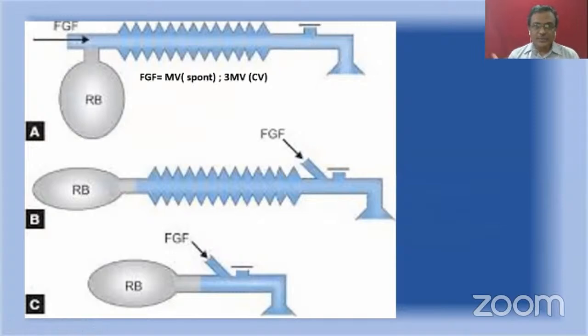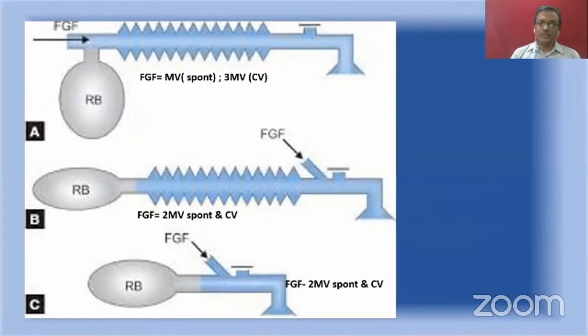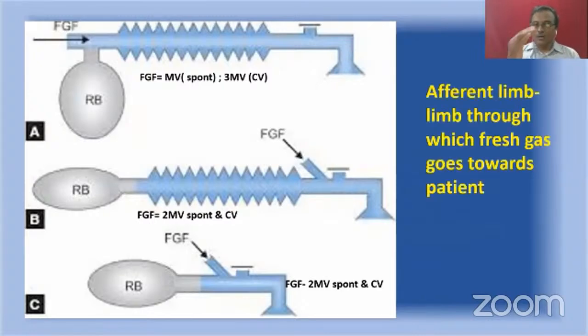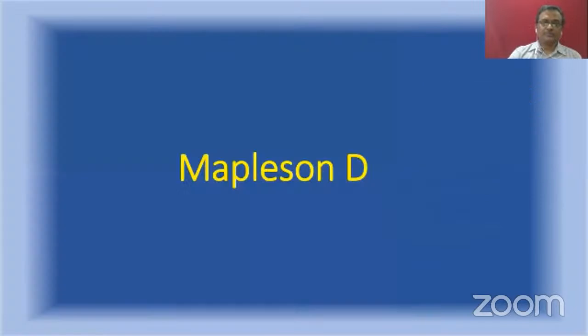And considering the physiology, the fresh gas flow requirement for Magill's or Mapleson A is minute ventilation for spontaneous breathing, 3 times minute ventilation for controlled ventilation, and for the other two, whether it is spontaneous or controlled, the fresh gas flow requirement is twice minute ventilation. And in all these A, B, and C, the reservoir is placed in the afferent limb.